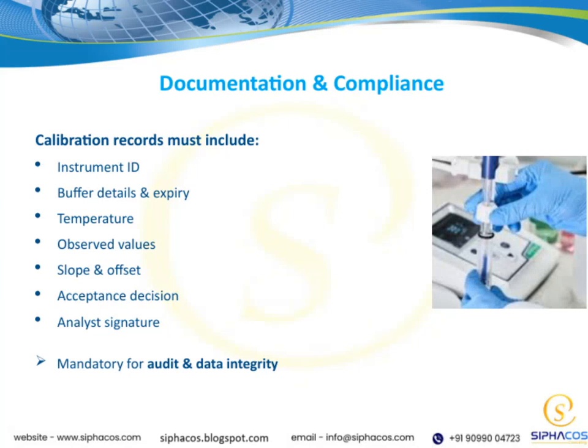Let's take a closer look at documentation and compliance when it comes to calibration records. It's essential that these records include several key details to ensure accuracy and traceability. First, we need to record the instrument ID, so we can always identify which instrument was calibrated. Then, buffer details and expiry dates are crucial because buffers can degrade over time, affecting the calibration. Temperature is another vital factor, as calibration conditions can influence results.